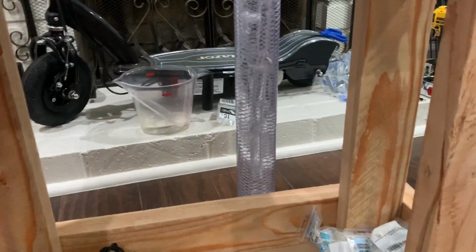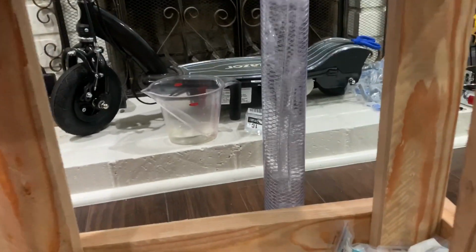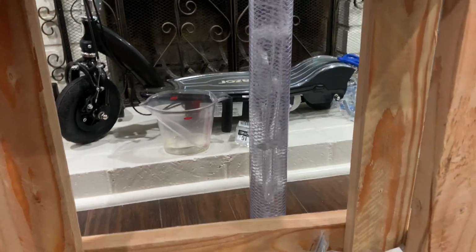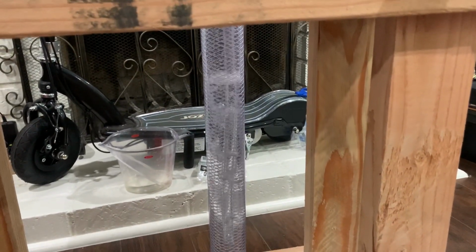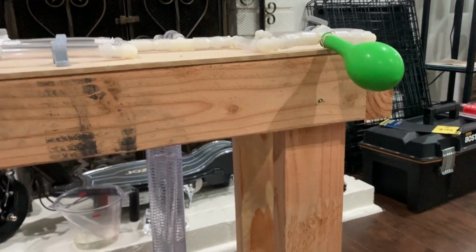And then the other thing that's important to note is that we are actually seeing bubbles from the plateau pressure portion of the system. So this is good. This means that that is working as expected, and that is preventing overpressurization of the lungs. So that means we know that this entire section is at whatever we set that pressure at, just around 29 centimeters of water pressure. If I close this valve, then you can see the lung maintains pressure because there's nowhere for it to vent. And then the bubbling through the plateau pressure stopped, indicating that there's no flow on the inspiratory leg of this section.